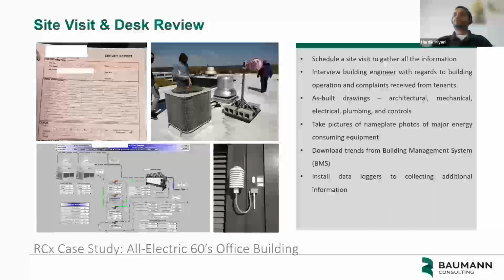Second question that we ask is, does the building engineer receive any complaints for the indoor air quality? Has the building engineer noticed any infiltration issues as part of this building? How often does he replace the filters, and how often does he calibrate the sensors in this building? So we asked this question to the building engineer and got the feedback, especially for the sensor calibration. That is something he has never calibrated in the past decade. So by interviewing the building engineer, we got to know these are also additional opportunities that we should be looking into.